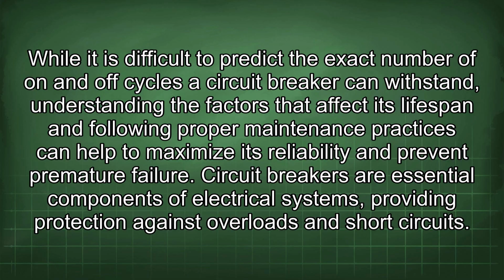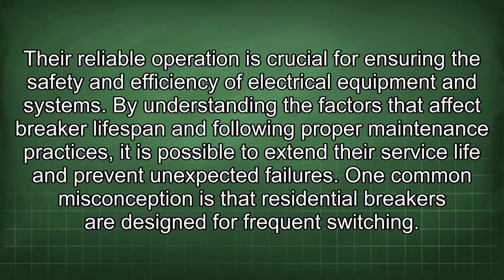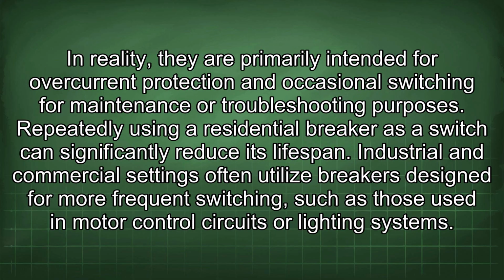failure. Circuit breakers are essential components of electrical systems, providing protection against overloads and short circuits. Their reliable operation is crucial for ensuring the safety and efficiency of electrical equipment and systems. By understanding the factors that affect breaker lifespan and following proper maintenance practices, it is possible to extend their service life and prevent unexpected failures. One common misconception is that residential breakers are designed for frequent switching. In reality, they are primarily intended for overcurrent protection and occasional switching for maintenance or troubleshooting purposes. Repeatedly using a residential breaker as a switch can significantly reduce its lifespan.